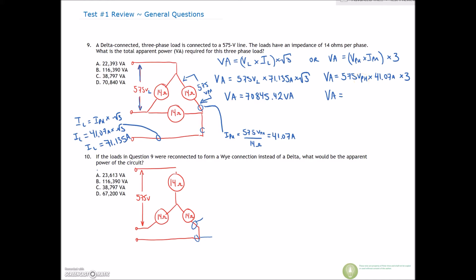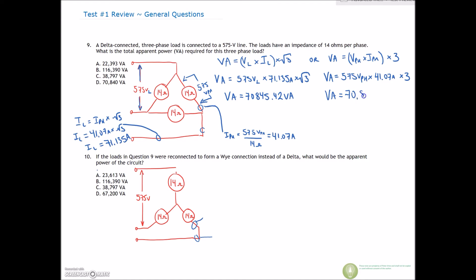Let's take a look at the phase values. We've got 575 volts multiplied by 41.07 amps, multiplied by 3 phases — that gives us 70,845.75. These are essentially the same value, so you can use either the line values or the phase values. Very close to answer D for our final answer.